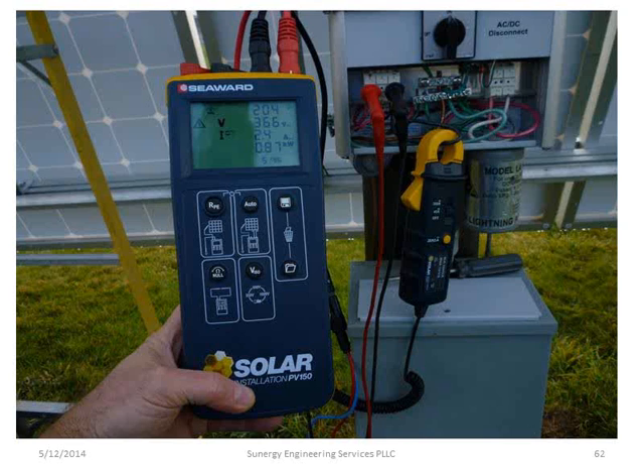And actually this one is the kilowatt hours, and you can see watts per meter at top, pretty low, 204 watts per meter. Not a very sunny day. Tells you what the open circuit voltage is. Actually, this is operational voltage, excuse me. This is what the array is operating at, and it's putting out 2.4 amps, which ends up being 0.87 kilowatts.